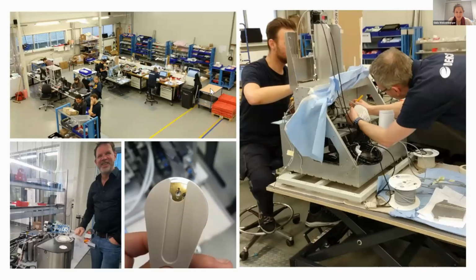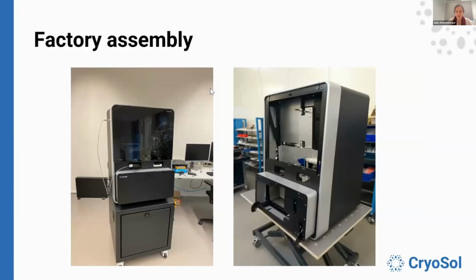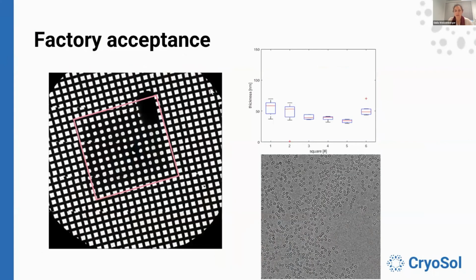And these are just a few pictures from the development, the assembly. The machines are also assembled at the factory. So here on the left is what the machine currently looks like. This is one of the machines that was actually shipped to one of the customers. That's the left image. On the right is still being assembled. The machines are assembled and they're accepted at the factory. So that means we work by depositing samples. We take a number of thickness measurements, test the protein, generally a standard protein, just to make sure everything's working fine. And then the machines are shipped.